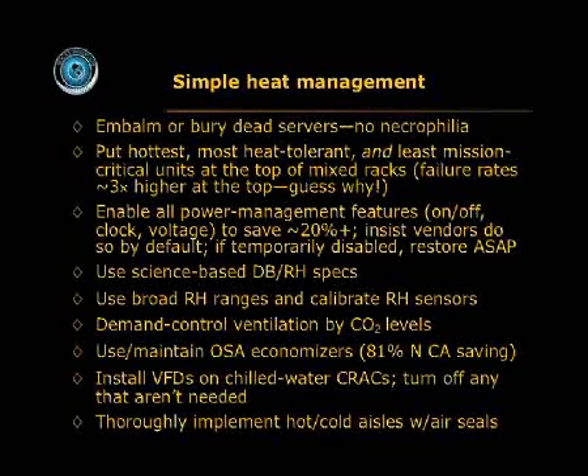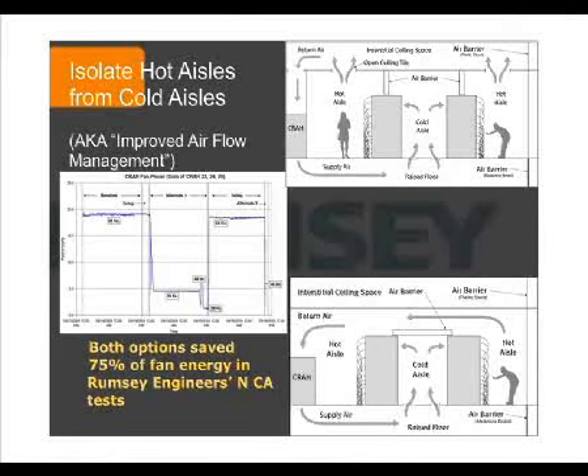Chilled water CRACs, it's very straightforward to put in variable frequency drives and turn off what you're not using. And of course, very fundamental, implement thoroughly and carefully hot and cold aisles with air seals. The concept is quite simple. Traditionally, you just have alternating hot and cold aisles, but the trouble is that unless you have an air barrier here or up above, they get mixed up. You'll get hot air spilling over into the cold aisle and so on. But using the kind of linear flow thinking that we have in clean rooms, you can even retrofit this kind of thing in an existing open plan data center. And when Rumsey did this in Northern California tests, either of these options would save 3/4 of the fan energy and get better uptime.